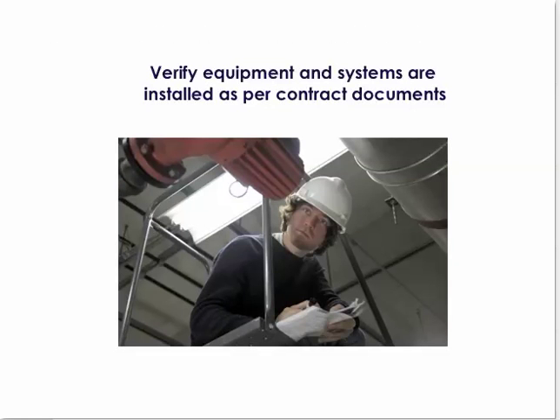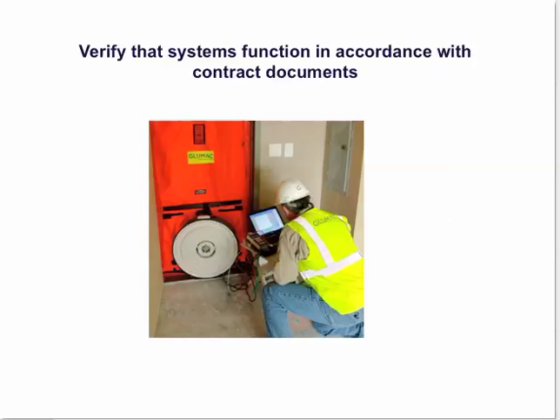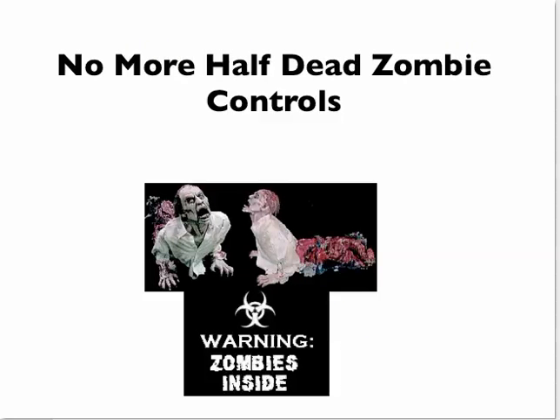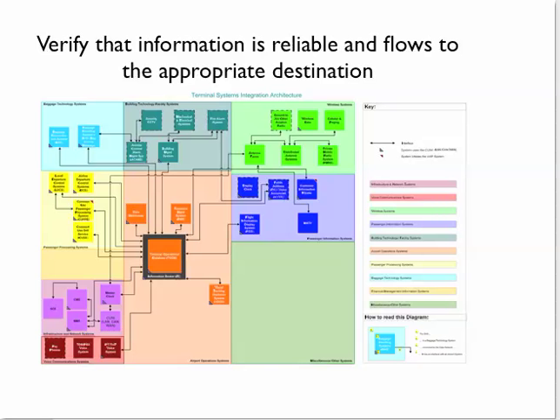Once we have the team fully understanding the commissioning process and bought into the commissioning plan, we need to start verifying that the equipment and systems are installed as per the contract documents, verify the systems function in accordance with the contract documents so that there's no more half-dead zombie controls out there, and verify that information is reliable and flows to the appropriate destination.